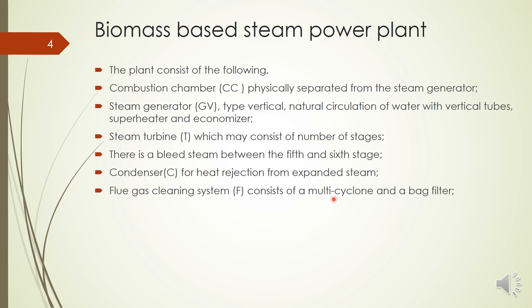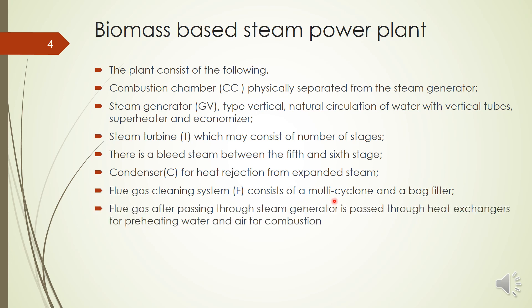A flue gas cleaning system is used before supplying flue gas to the atmosphere, with the help of a cyclone separator and bag filter, for reducing emissions. The flue gas, after passing through the steam generator, is passed through the heat exchangers for preheating the water and air for combustion. These are some of the components used in this biomass-based steam power plant.